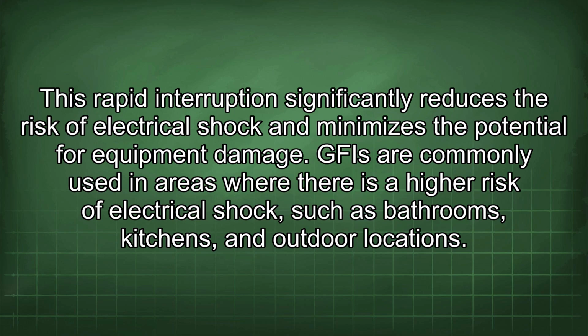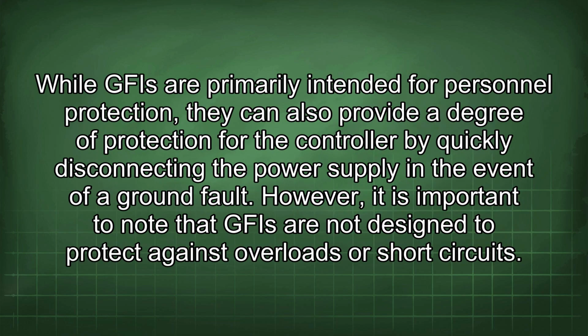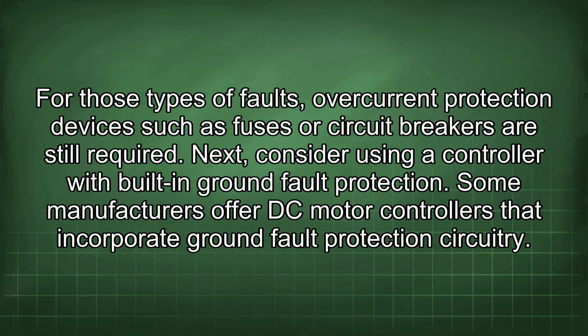GFIs are commonly used in areas where there is a higher risk of electrical shock, such as bathrooms, kitchens, and outdoor locations. While GFIs are primarily intended for personnel protection, they can also provide a degree of protection for the controller by quickly disconnecting the power supply in the event of a ground fault. However, it is important to note that GFIs are not designed to protect against overloads or short circuits. For those types of faults, overcurrent protection devices such as fuses or circuit breakers are still required.